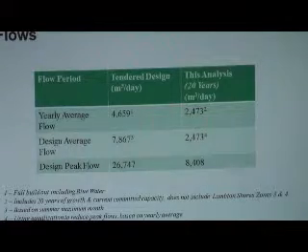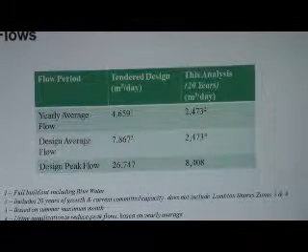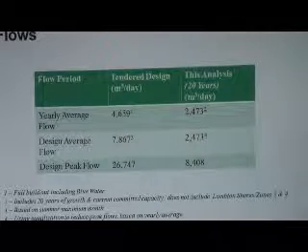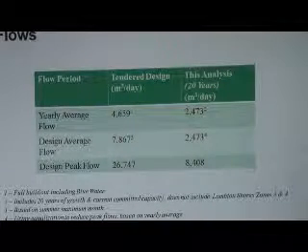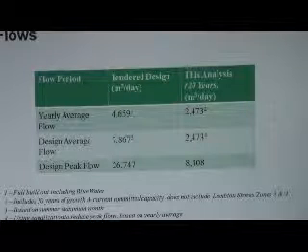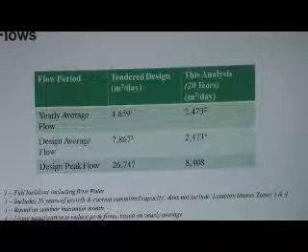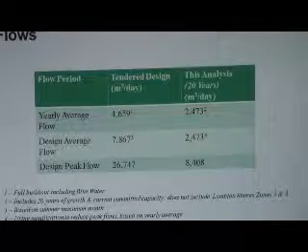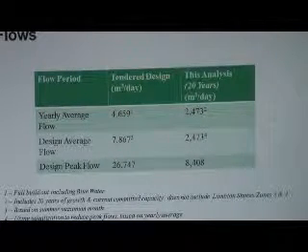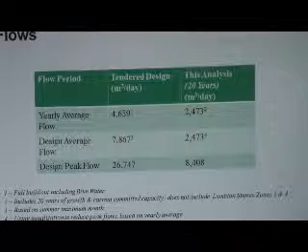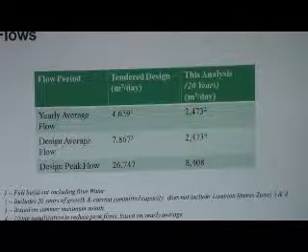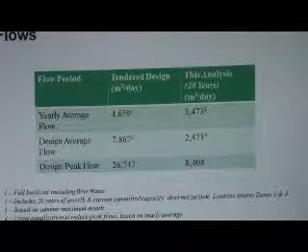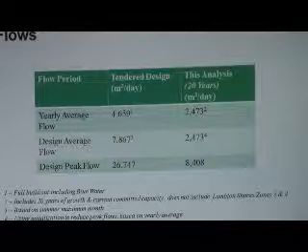So just to go back, and I think I'm repeating myself, the tender design was 4659 cubic meters a day. The 20-year flows that we're looking at now are 2473, and actually because they designed for the peak month, which is the July-August period, they designed it for 7867 cubic meters a day. Now one of our options is to use equalization, which then brings our design back to the 2473.